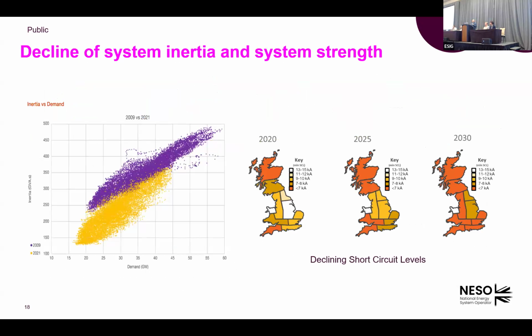Let's give some examples of how the system is actually changing. We can clearly see that inertia has been changing massively over the last 10 or 20 years. We're also starting to see system strength, as measured in fault levels, decreasing in the future, because IBRs generally generate much less fault current during a fault compared to synchronous machines.